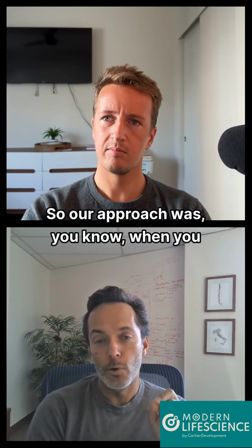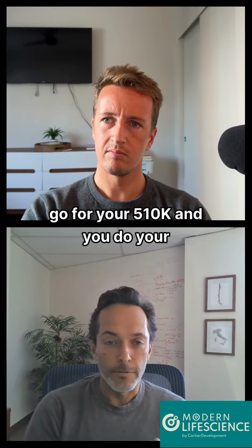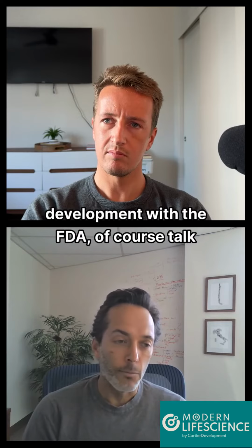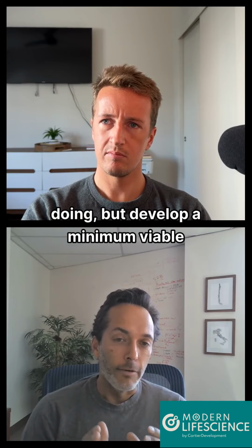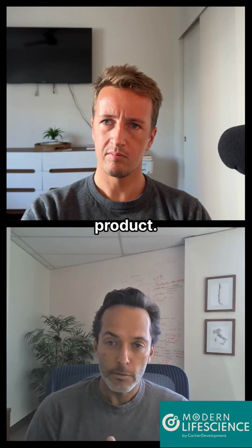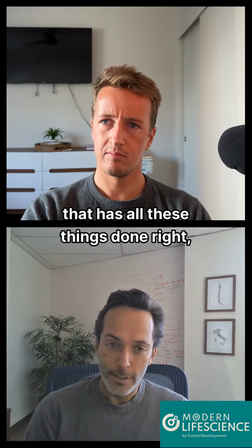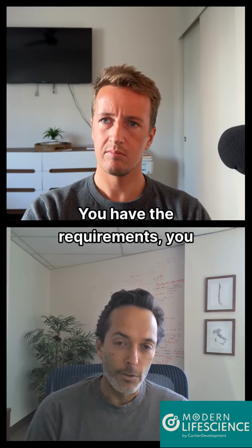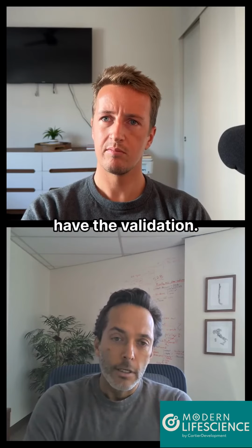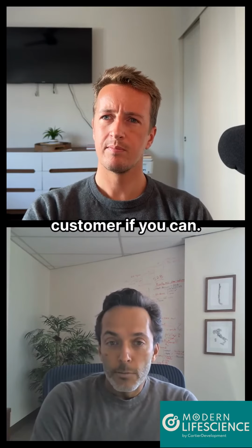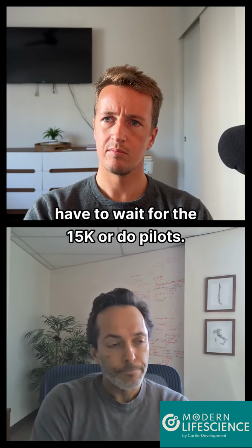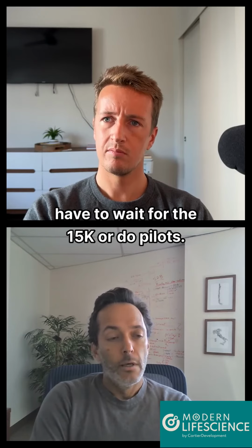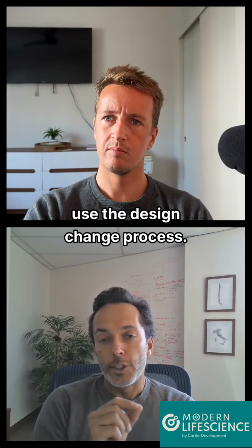So our approach was, when you go for your 510K and you do your development with the FDA, of course, talk to the FDA and explain what you're doing, but develop a minimum viable product that has all these things done right. You have the requirements, you have the verification, you have the validation. Put that in the hands of the customer if you can. And of course, it's regulated, so you have to wait for the 510K or do pilots. And then use the design change process.